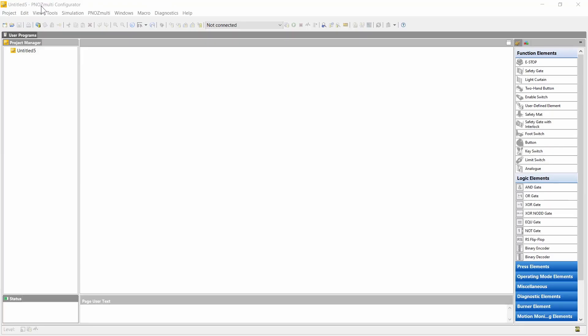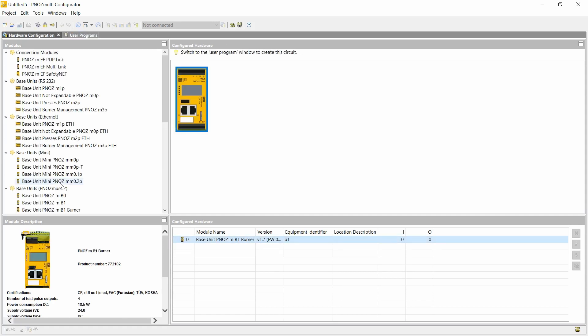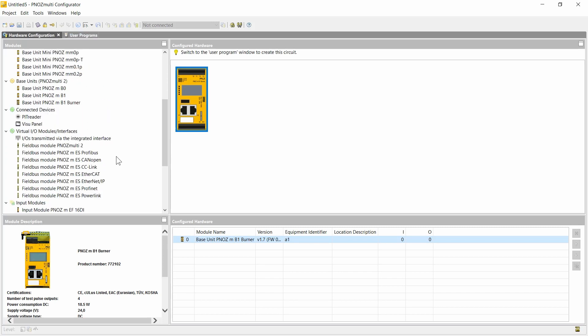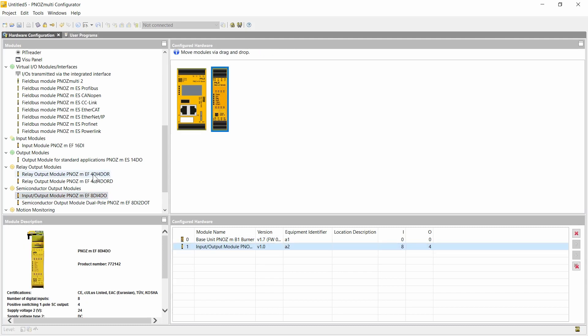Now I'm going to show you how this function block is configured. In the first step we configure the hardware. We start with the base unit, in this case the PNOZ m B1 burner, and then we add some IO modules — for instance a module with eight inputs and four semiconductor outputs and a relay module.